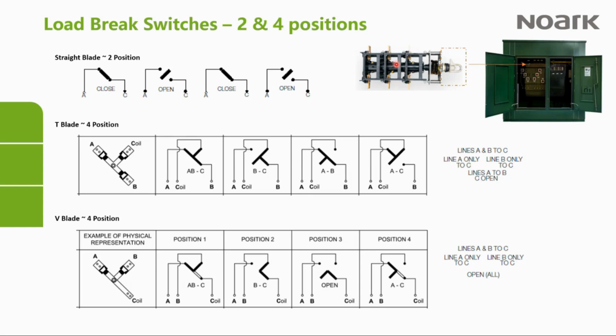So you can see this part is what you see at the front, and all of this part is right inside the transformer. So it's a simple switch that allows us to switch. These are the different positions here. For example, if we want the transformer to be in the loop configuration, then the power comes from A, and then it leaves through B, at the same time feeding the transformer coil. So that is one position.